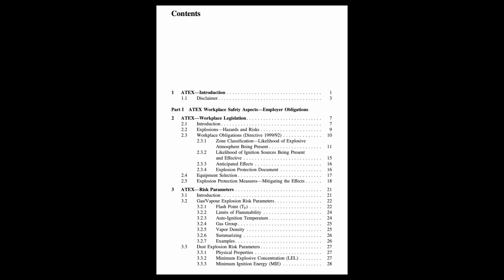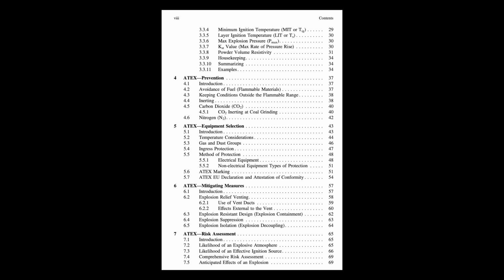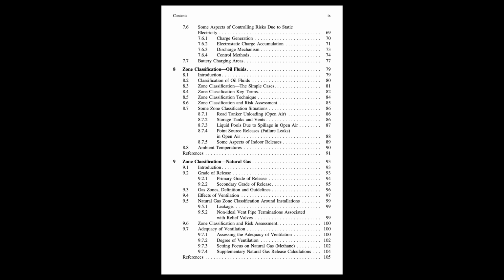What about the practical side of using CO2? Like how much can you actually deliver? Yeah, the guide mentions that your delivery capacity, how much CO2 gas you can get out, mainly depends on the size of the vaporizer, the bit that turns the liquid into gas, and the ambient temperature. Exactly. Colder weather can reduce the vaporization rate. It also notes that while low-pressure systems might seem like they'd use more energy for cooling, they're often preferred for larger-scale needs, especially in warmer climates, because they can offer higher discharge rates. Interesting trade-offs.